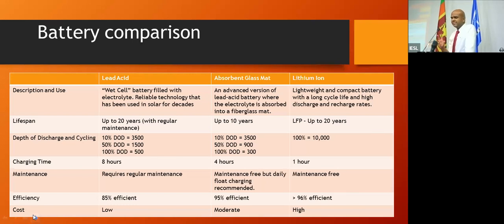The AGM battery is basically the sealed battery - it's a variant of the lead acid battery. The advantage of the AGM is it has lower internal resistance. A lead acid battery has internal resistance of about 10 to 12%, while a sealed battery is about 2%. So you can charge and discharge these batteries very quickly. But the issue is if you don't give the ideal current, sealed batteries will fail very fast, because lead acid batteries are very tolerant of high currents when charging. If you mess around with the AGM like that, you'll kill it.